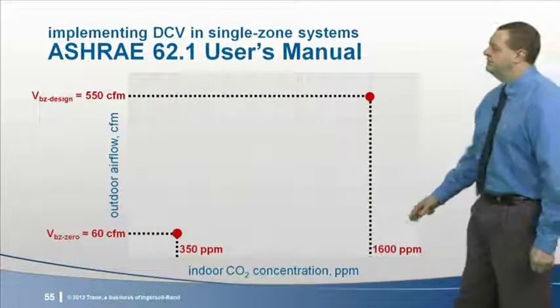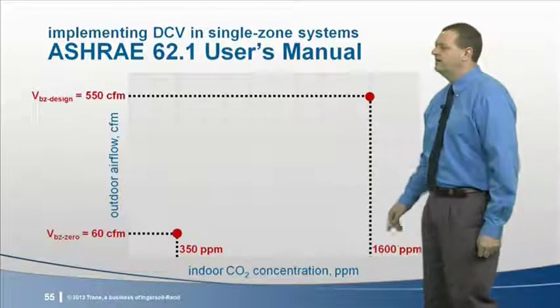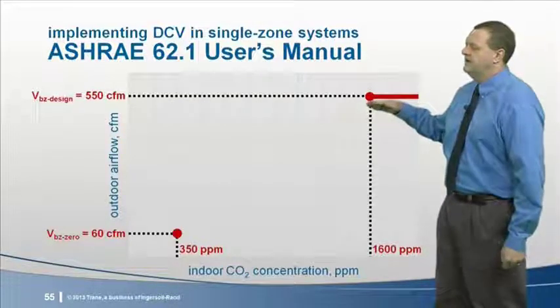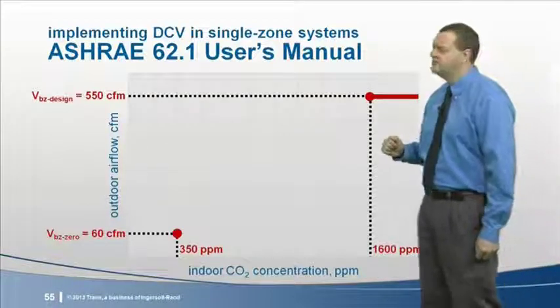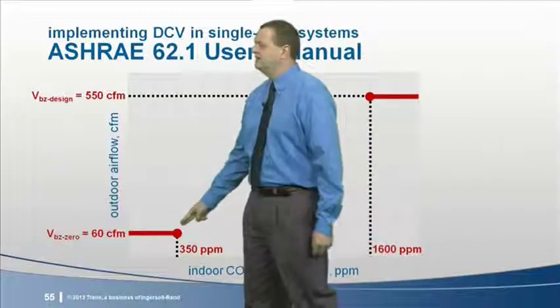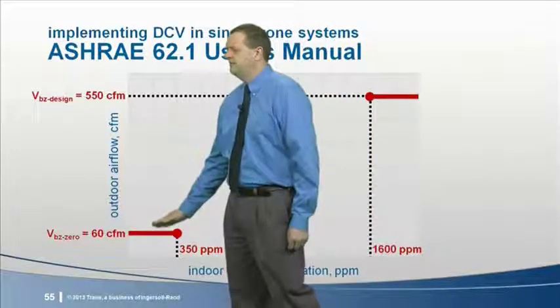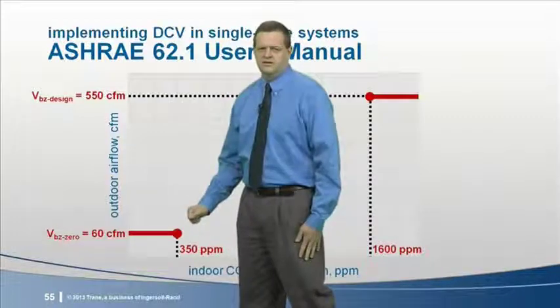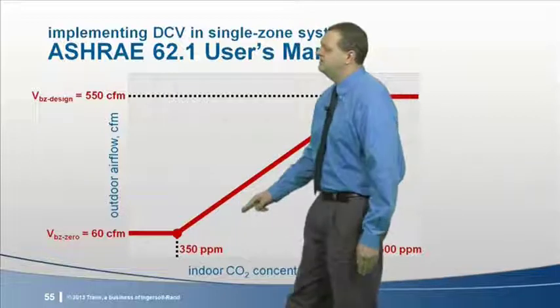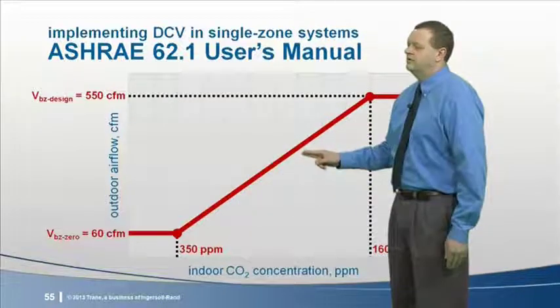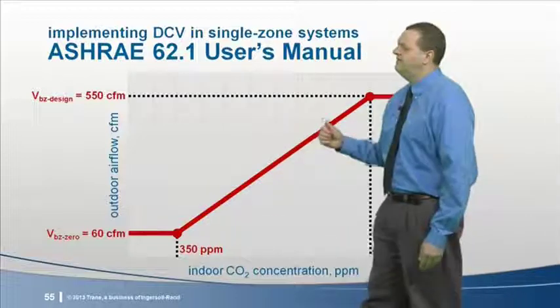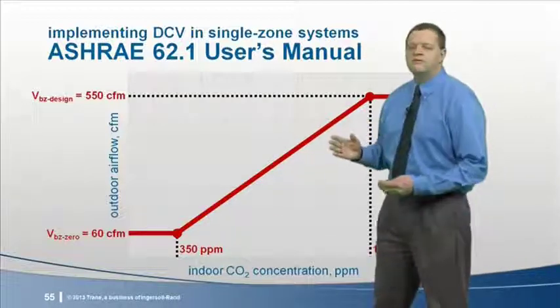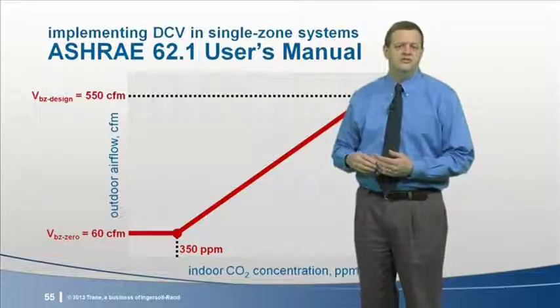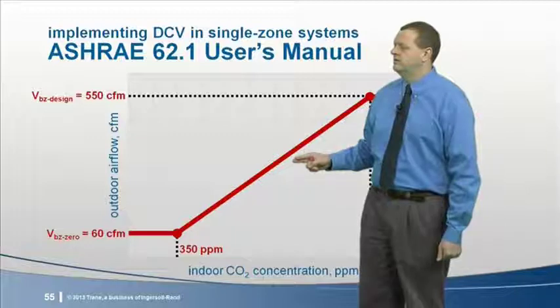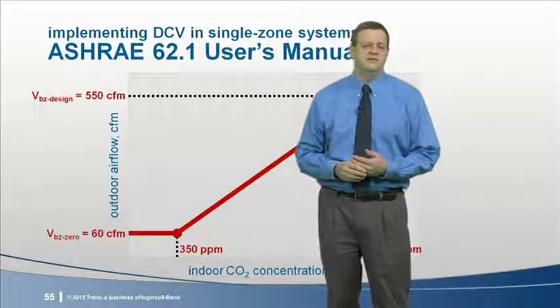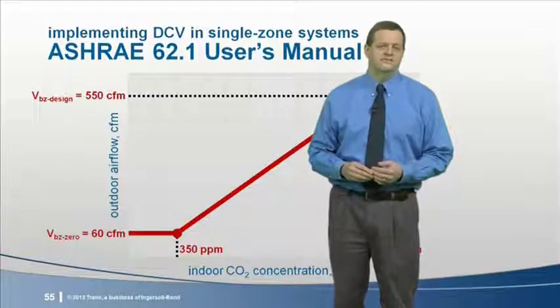When the space CO2 concentration equals 1,600 parts per million or higher, the outdoor air damper modulates to bring in the design outdoor airflow of 550 CFM. When the concentration is 350 or less, the damper modulates to bring in 60 CFM, which is the building component of the ventilation rate. And when the CO2 concentration is between these two limits, the controller modulates the outdoor air damper proportionally between 60 and 550 CFM. Now, if the system has a flow measuring damper, it just controls to this new CFM set point. But if proportional damper control is being used, it takes a bit more engineering of the controller.